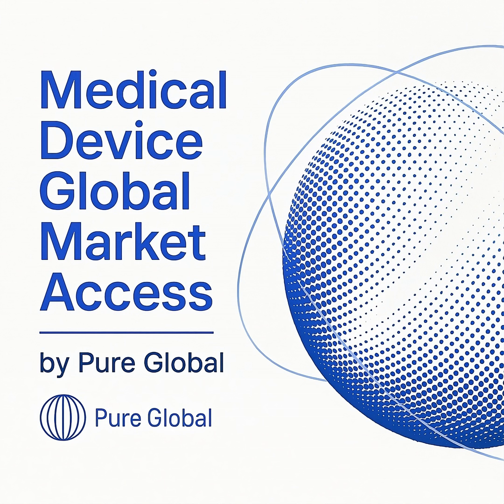Today, we are exploring the single most important standard for any medical device manufacturer with global ambitions: ISO 13485:2016, the international standard for a medical device quality management system, or QMS. Its formal title is Medical Devices, Quality Management Systems, Requirements for Regulatory Purposes, and that last part is the key. Unlike other quality standards, its primary focus is ensuring you can consistently meet customer and, most importantly, evolving regulatory requirements worldwide. The current version of the standard was published in March 2016, replacing the previous 2003 version.